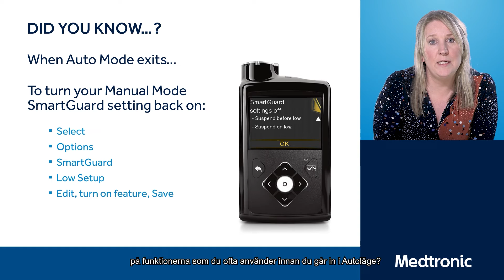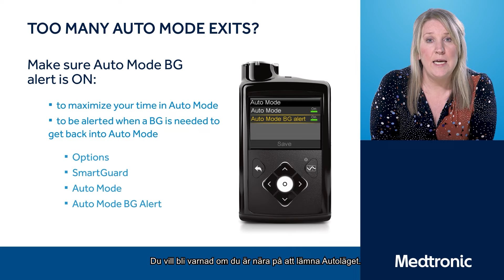If you're receiving too many auto mode exits, it may be because you've got your auto mode BG alert switched off. Occasionally in clinic we've found that these have been switched off accidentally. And where we want to maximise your time spent in auto mode, it's a good idea to have these switched on. Here again on the screens are the instructions of how to go back in and switch that on. You want to be alerted and notified if you're going to be exited at any point.